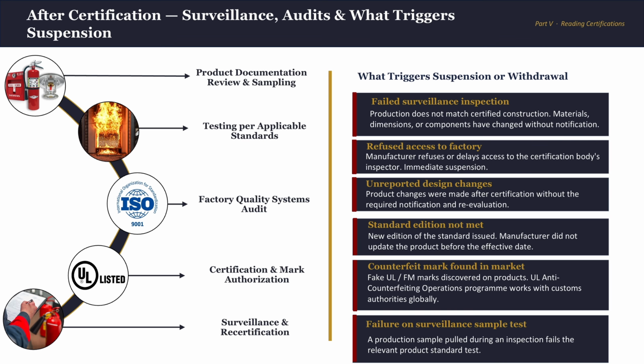After the product is fully documented, testing must happen per the applicable standard. The product goes to an accredited laboratory. A fire test is conducted against the required standard. The specimen passes, obviously. Then the results are recorded, and this is the technical evidence behind the certification. After that, the quality management system or factory quality system audit. What does that mean and how is that relevant? The certification body audits the manufacturing facility.